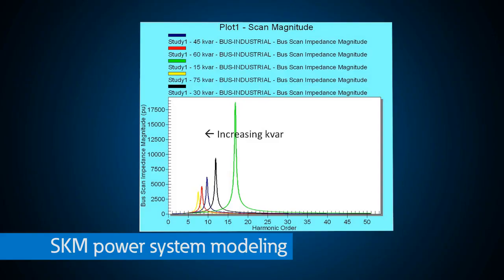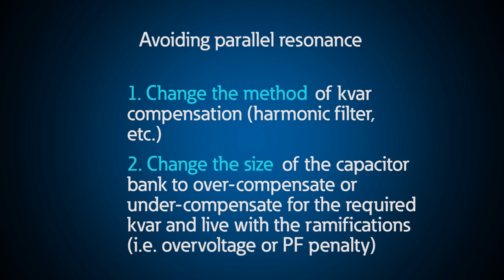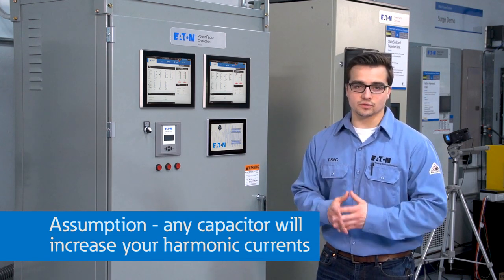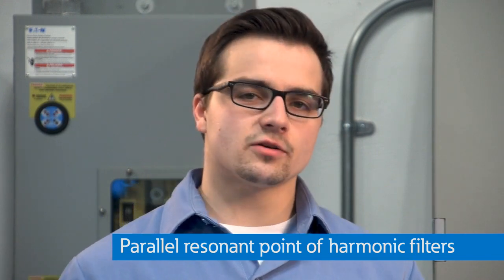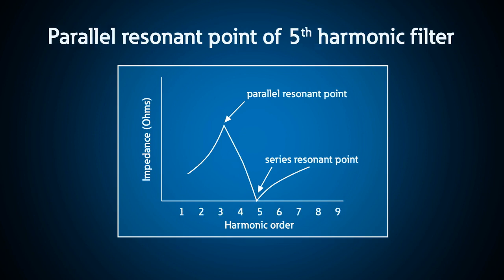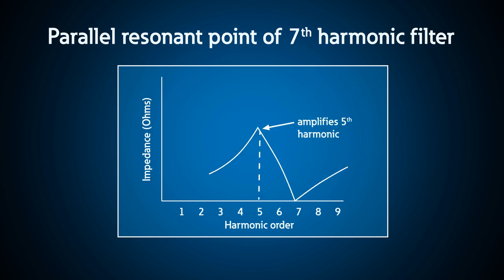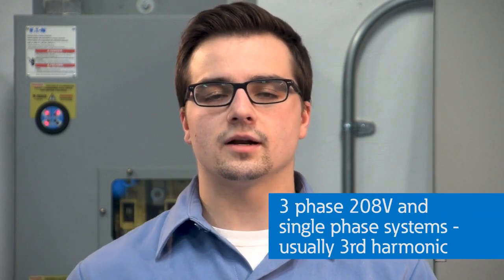Power system modeling programs like SKM can help you visualize the effects of resonant circuits and the amplification factor. This SKM frequency scan curve for our demo system illustrates the points at which various stages of capacitors will create problematic conditions. Avoiding parallel resonance can be done by changing the size of the capacitor, but then you may have other issues with power factor penalties. You can assume that any capacitor will always increase your harmonic current on the system — the question is how close are you to resonance and how much will harmonic currents increase? Another important thing to consider is the parallel resonant point of harmonic filters, which in general is one or two harmonic orders less than the tuning point. So for a 5th harmonic filter that would be around the 3rd or 4th, but for a 7th harmonic filter the parallel resonant point is just above the 5th harmonic. This illustrates a specific problem with multi-stage filters where the tuning point must be at the lowest expected harmonic — usually 5th harmonic for three-phase loads and 3rd harmonic for single-phase loads.